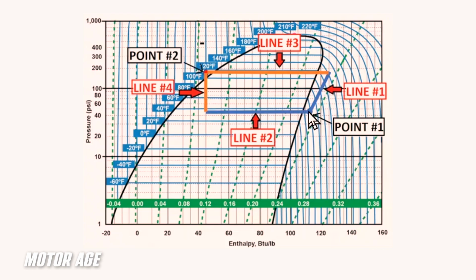If this line plotted fell too far within this bell curve, it would still be liquefied and we could slug the compressor. So again, the superheat, anything above or to the right of this black bell curve indicates superheat, and that's desirable. We need some superheat to ensure that the refrigerant remains in a gaseous state when it feeds the compressor. Once the temperature of the refrigerant sheds 20 to 30 degrees Fahrenheit here of superheat, it will then begin to change states from a gas to a liquid, and that's exactly what we're witnessing right here.